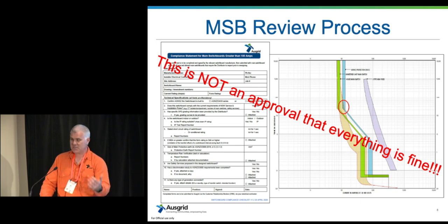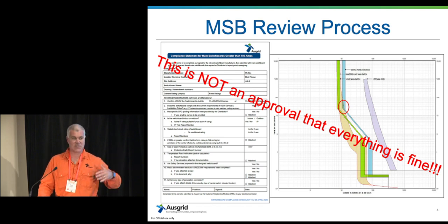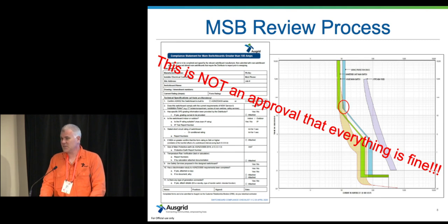As an inspector, as a DNSP, we are not saying that your switchboard doesn't comply. You just have not yet proven that it does. That's what Max was talking about before, the certification and documentation required to prove that compliance. That is generally what's missing. So if you're consultants or contractors in the room, make sure that the switchboard you're buying is backed with that compliance documentation. Otherwise, you might be spending a significant sum of money for it to turn into scrap. You might be able to recycle some copper and some functional units out of it, but everything else is going to go to the tip, and then you're going to be rebuilding another board.